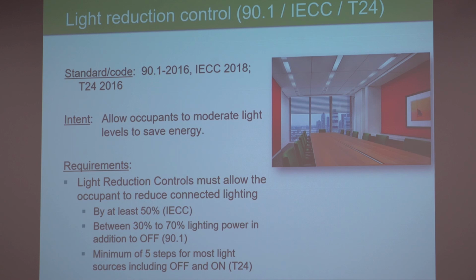Light reduction controls have been in the energy codes for a while. Basically, the key here is to give occupants an additional light level in addition to just full on and off. IECC requires a 50% level, so on, full off, and at least 50%. ASHRAE requires at least a level between 30 and 70%. California Title 24 actually requires, especially if you're doing LED lighting, dimming in nearly every space. And of course, if you did dimming, that complies. One key exception in IECC is if your space is controlled with an occupant sensor, then you don't have to provide the multi-level lighting.